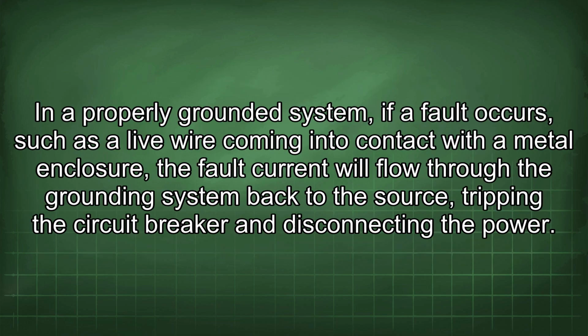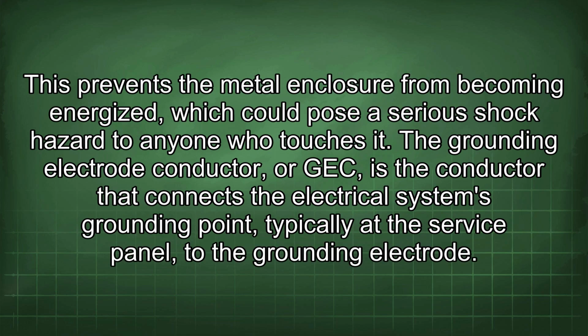In a properly grounded system, if a fault occurs, such as a live wire coming into contact with a metal enclosure, the fault current will flow through the grounding system back to the source, tripping the circuit breaker and disconnecting the power. This prevents the metal enclosure from becoming energized, which could pose a serious shock hazard to anyone who touches it.